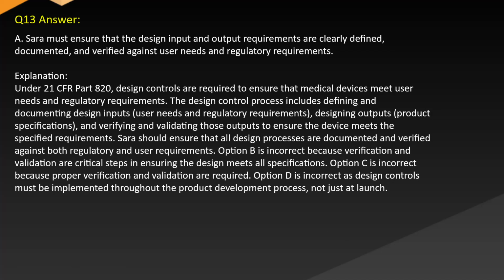Answer A. Sara must ensure that the design input and output requirements are clearly defined, documented, and verified against user needs and regulatory requirements. Explanation. Under 21 CFR Part 820, design controls are required to ensure that medical devices meet user needs and regulatory requirements. The design control process includes defining and documenting design inputs, user needs, regulatory requirements, design outputs, product specifications, and verifying and validating those outputs to ensure the device meets the specified requirements. Sara should ensure that all design processes are documented and verified against both regulatory and user requirements.